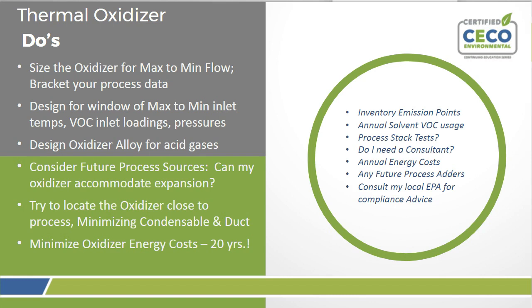So to kind of review here, before we get into some examples, thermal oxidizer do's, we decided we're gonna be optimistic here and just focus on what you should do. So size the oxidizer for maximum and minimum flow, bracketing process data. This is really important. One of the worst things you could do is to just undersize the unit. It's a major capital expenditure, and essentially there's not a lot you can do other than redesigning the whole thing or putting in an additional oxidizer.